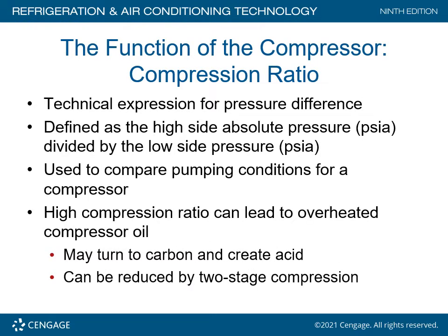Compression ratio is very important when determining if compressors are operating correctly. It is a technical expression for pressure difference, defined as the high side absolute pressure (PSIA) divided by the low side PSIA. The 'A' stands for absolute. You take the existing pressure you record and add 15, which compensates for atmospheric conditions in most cases.